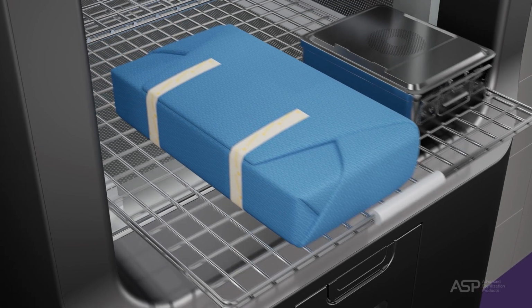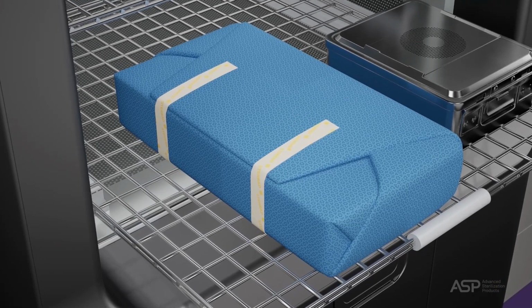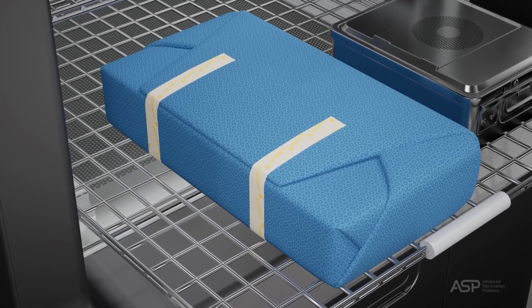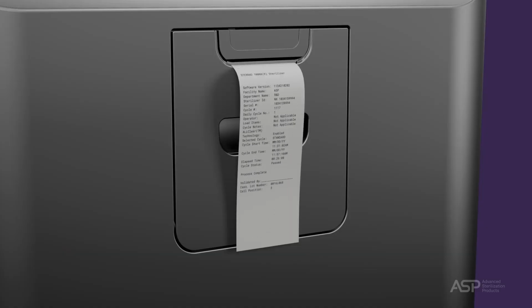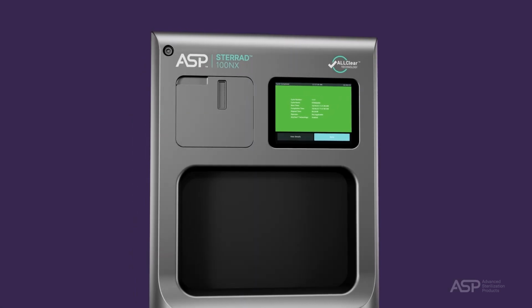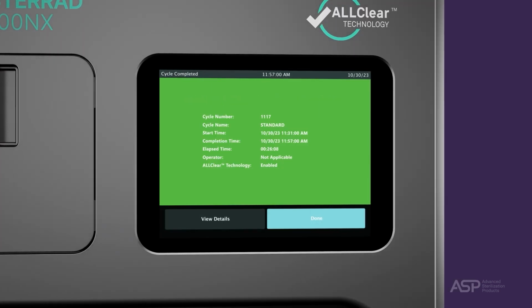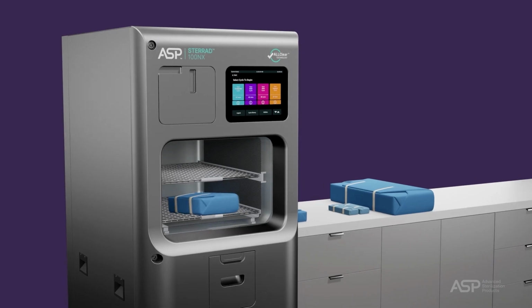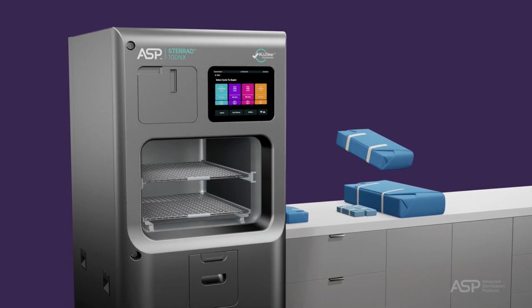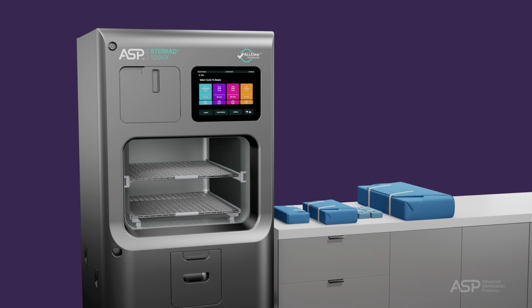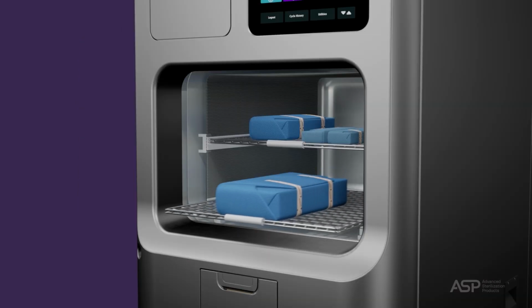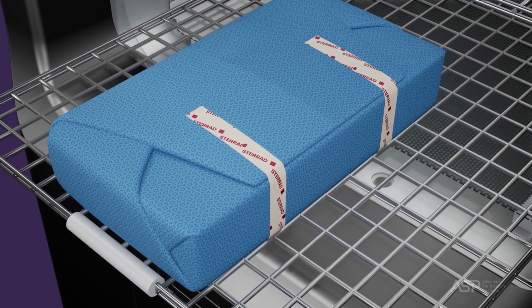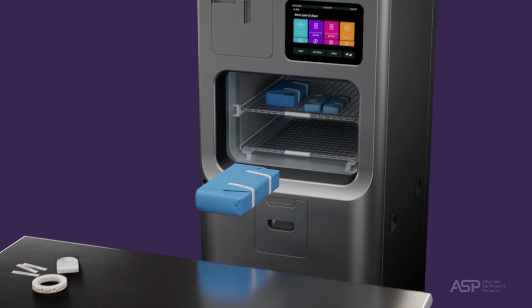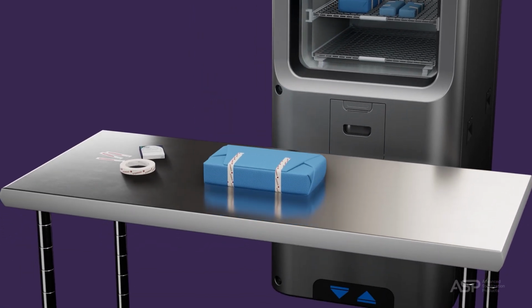Ensure that the chemical indicators on or in the sterilized packages exhibit the correct color change, and that the cycle printout shows that all parameters were met. Additionally, the system screen will display the cycle status as process complete. The load is now ready for immediate use following your hospital or healthcare facility's policy. If the chemical indicators do not exhibit the correct color change, investigate the cause, and then repackage the devices and reprocess.